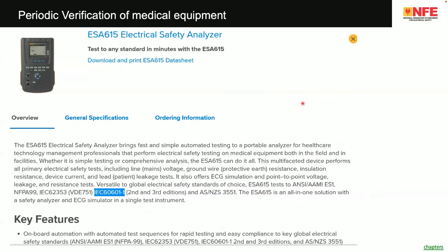Periodic verification of medical equipment: the IEC standard, there is an IS standard 62353. It explains that every biomedical equipment has to be tested. That means you have to have a meter like this. You have to test the biomedical equipment once in a while. Then only the fire and accidents from this equipment can be reduced.